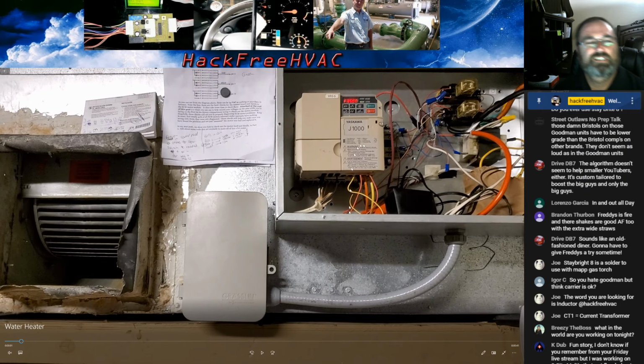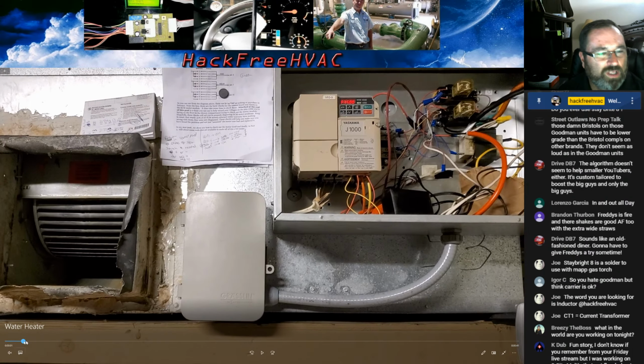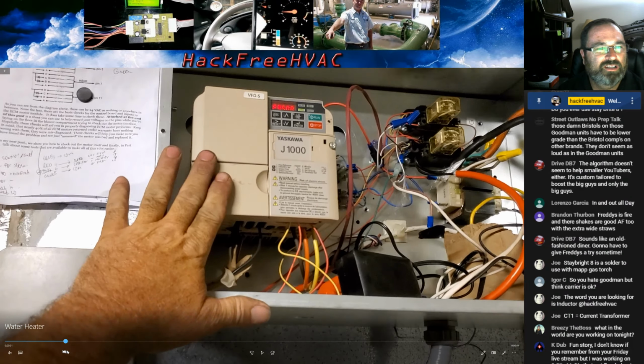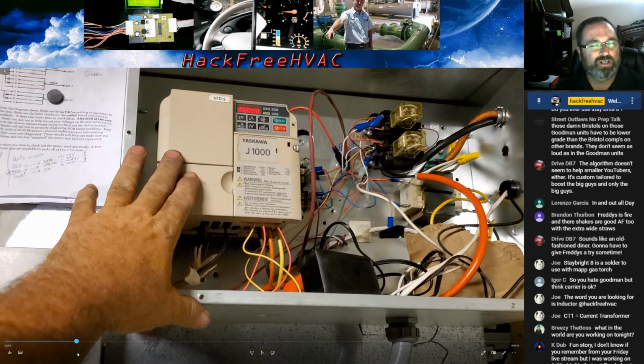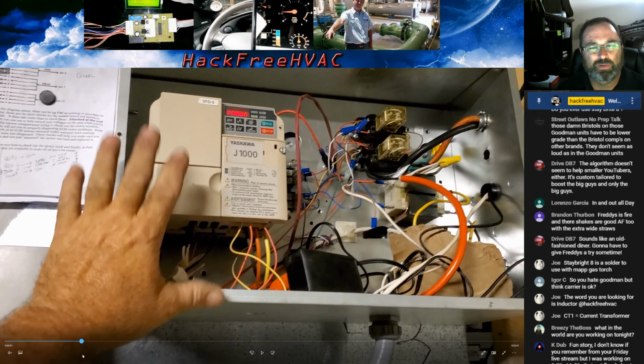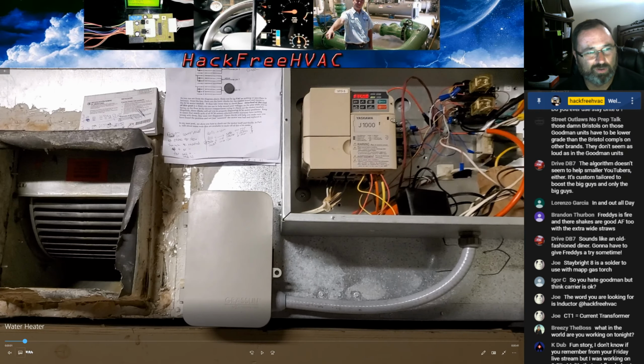So this thing here is a water source heat pump I've had for a while, and I changed it - pulled out the 310 compressor and put in a 210. It was a 460 volt water source heat pump, so I put an ECM that runs on 230 in here, and then a 230 volt 3-phase compressor, with the VFD. So I have single phase power coming in and 3-phase going out, and right here it's running 35 hertz.